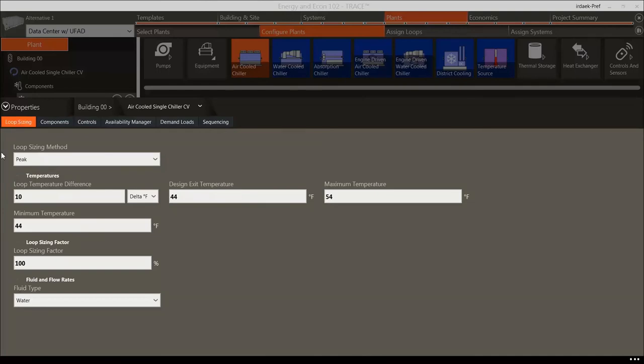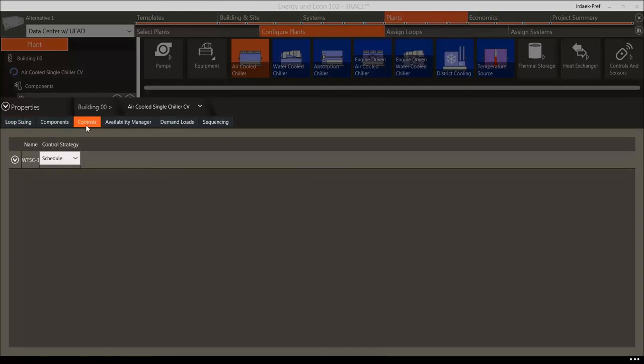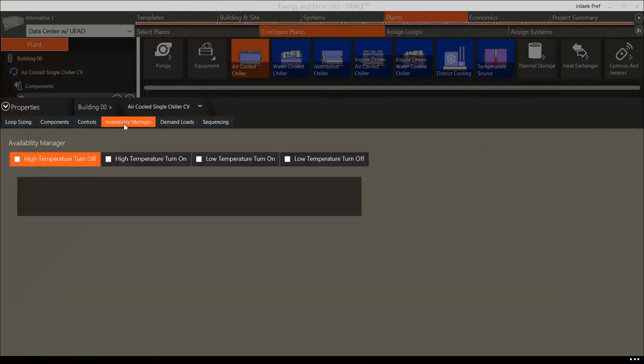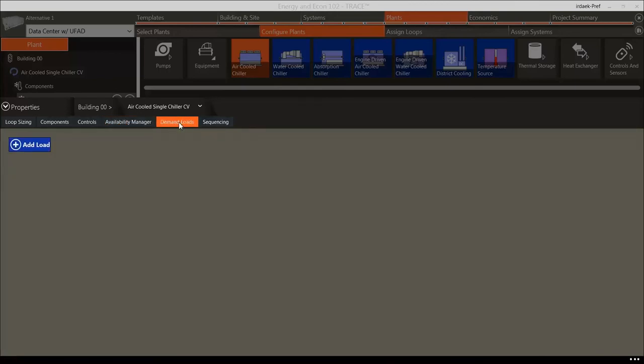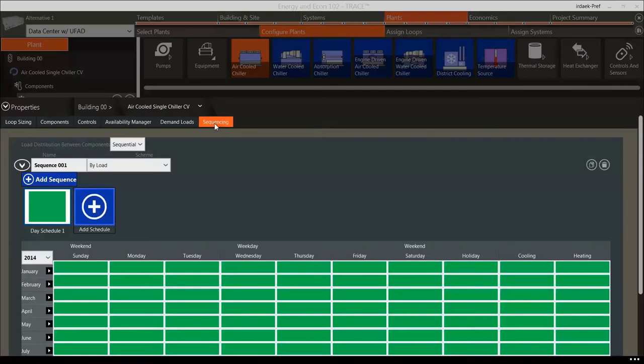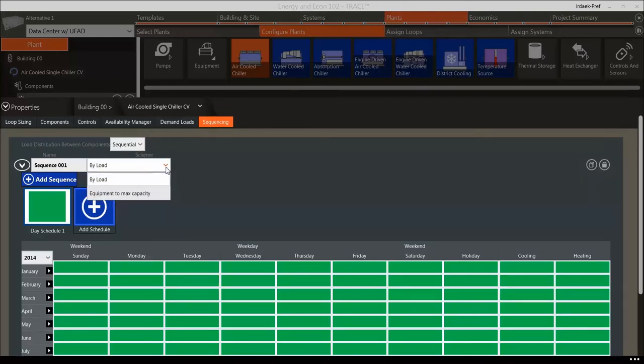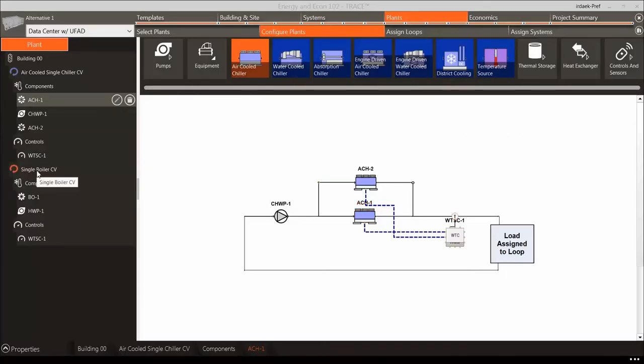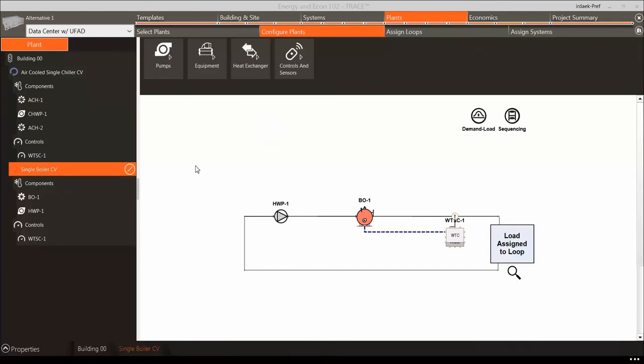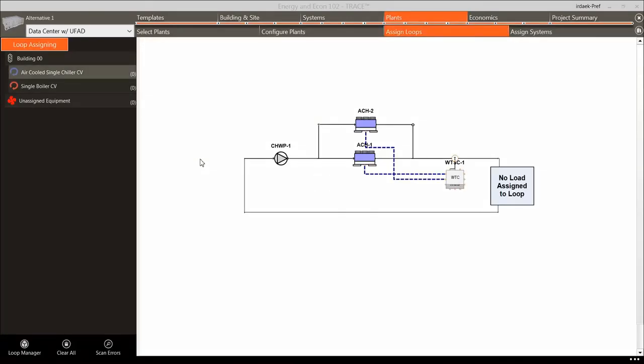Loop Sizing contains inputs for design temperatures and fluid types. Controls dictate what temperatures the loop will be controlled to. Availability Managers are controls for turning the loop on and off. Demand Loads are process loads such as domestic hot water or manufacturing processes that aren't building loads. Sequencing allows you to define which chiller turns on first and how the chillers operate together. Now that we have finished configuring the chilled water loop, we can do the same to the hot water loop. For simplicity, we'll use the default design and simulation parameters for that loop.